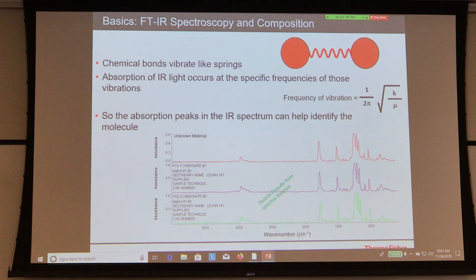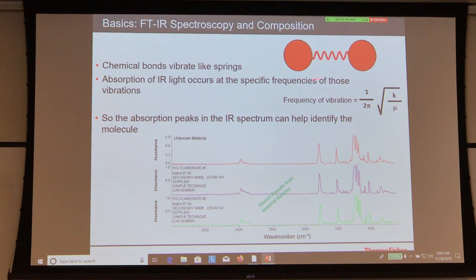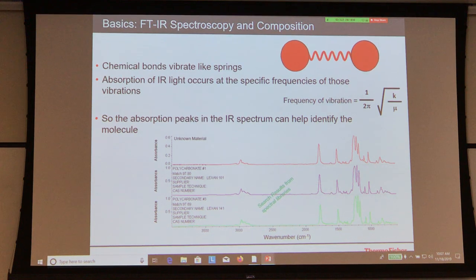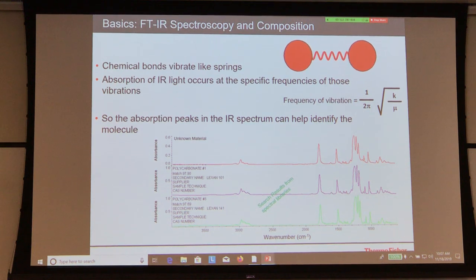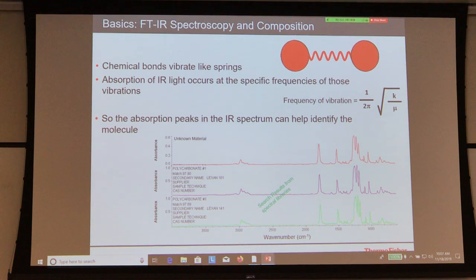The frequency of vibration is inversely proportional to the mass of the atoms — the lower the mass, the higher the wavenumber you're going to see; the heavier the atoms, the lower the wavenumber. Once we run a sample, we get a spectrum. Here we have a simple spectrum of polycarbonate. How do we know it's polycarbonate? We run it against a standard library. That's where libraries become very important, and we'll address this in detail this afternoon.